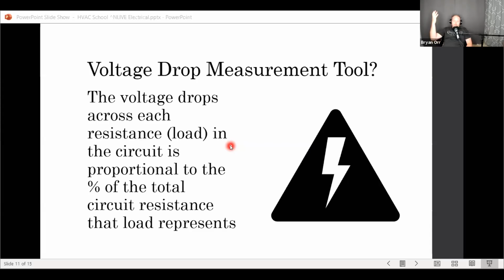In the case of, let's use an example, a compressor, that'd be the compressor windings. In a contactor on the Y circuit, that would be the contactor coil, right? So you'd measure 27 volts or whatever it is across the contactor coil. But if you add another voltage drop in series with that load on that same path, then that voltage drop, depending on what percentage of the resistance it is, is going to be what percentage of the voltage drop it is. And so this is how we can use our meters to find things that are undesigned, poor connectivity, whatever, and we can use our meters to find problems in the circuit.